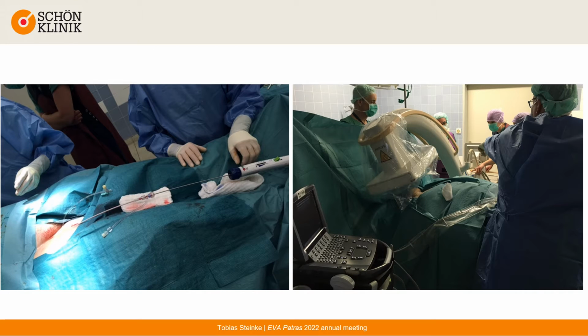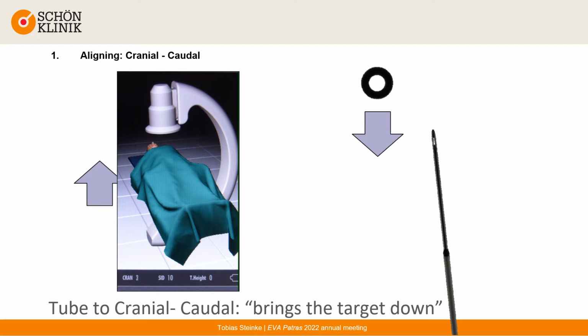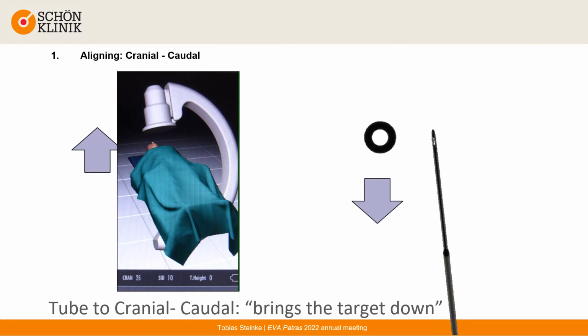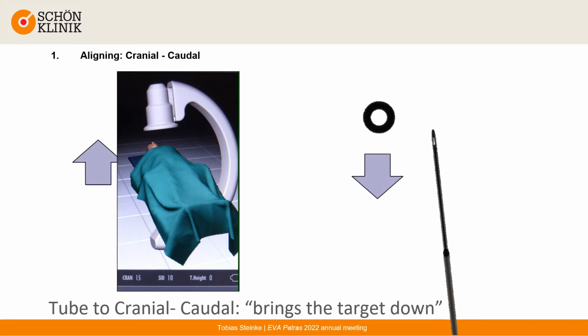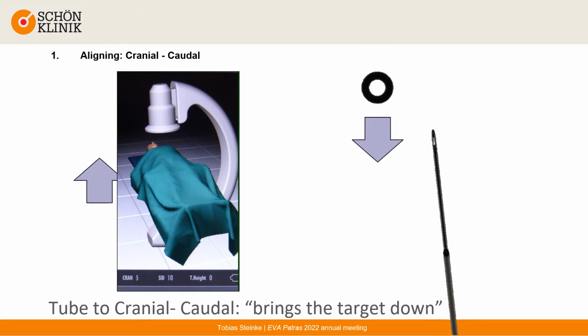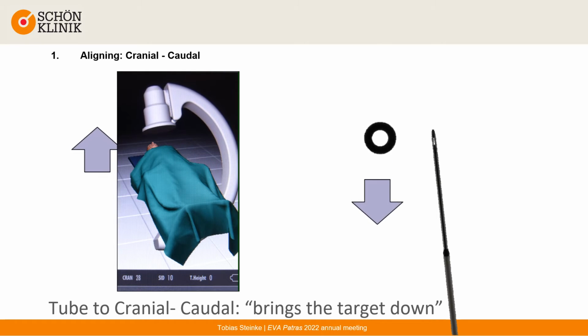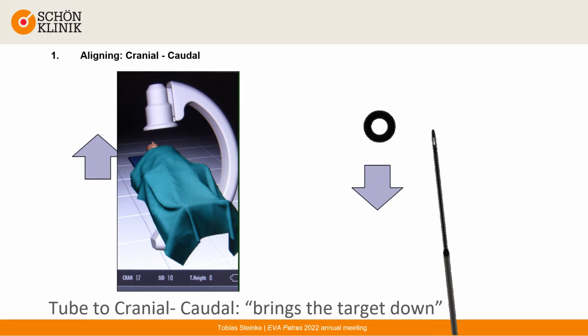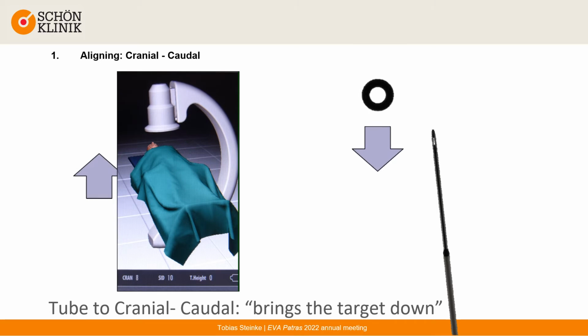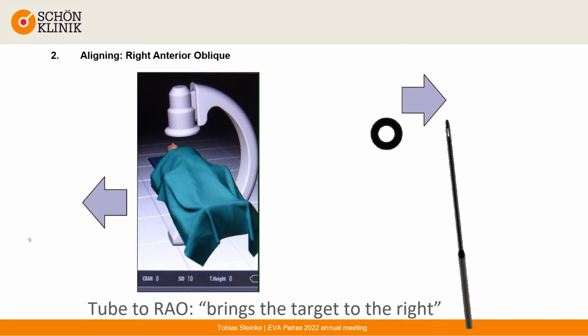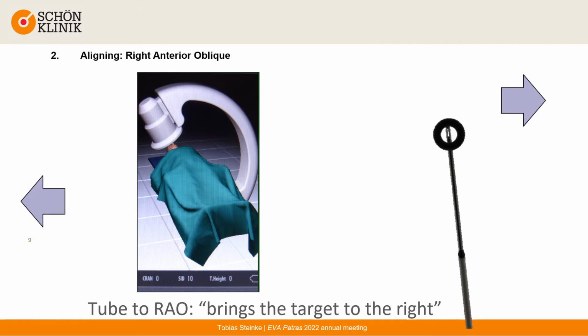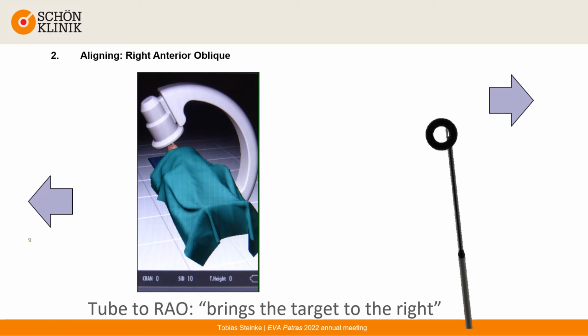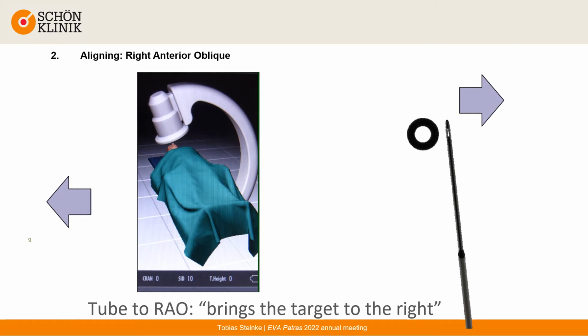And here you see how it looks in reality. You bring in the steel rod over the groin, the right side of the patient, and you adjust the C-arm to have the best view and to bring out the sharp wire at the neck. Adjusting the tube properly is just the key to success. And that has to be done in two different planes to get the best view and to bring out the steel wire at the place where you really want to have the exit.